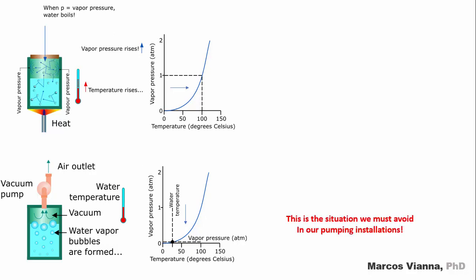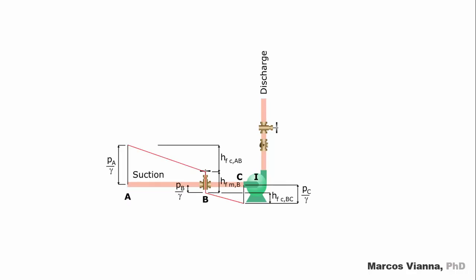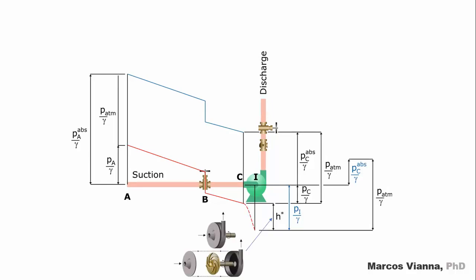Now let's consider this pump with its suction and discharge pipes. This red line is the hydraulic grade line, which represents the pressure variation along the flow and the head losses that occur. To find it, we add the atmospheric pressure to the pressures represented by the red line. The atmospheric pressure varies with the altitude. There is a head loss, designated by H-star, which we cannot calculate. It occurs inside the pump, from its entrance to the center of the impeller. Only the manufacturer can tell its value.